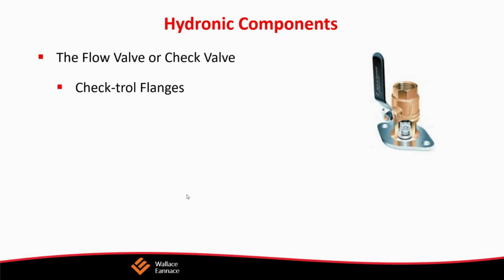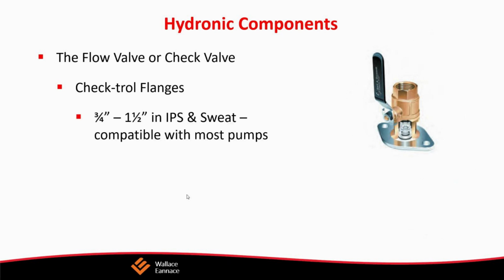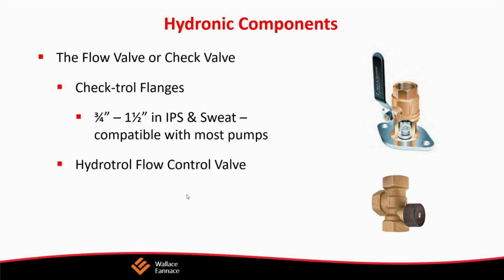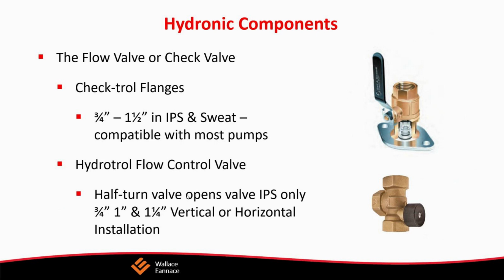Let's talk about flow or check valves. There's a couple of choices there. Why do we need flow control valves? Well, it's not really to control the flow. It's really to prevent overheating and crossover. Inside a pipe, gravity flow will occur when a pump is off. Cooler water will fall, warmer water will rise.